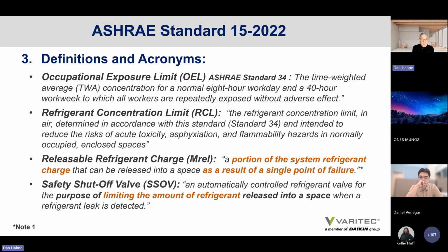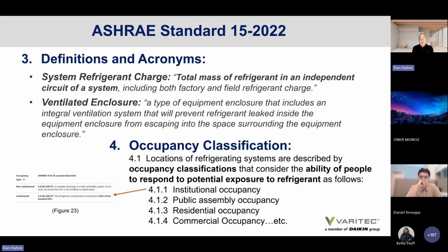There's releasable refrigerant charge, and this is an important component in evaluating whether or not a VRV system meets the RCL limits in the smallest occupied space served by a VRV system. Releasable refrigerant charge is a portion of a system refrigerant charge that can be released into a space as a result of a single point of failure. In other words, one refrigerant circuit. Another term is a safety shutoff valve, an automatically controlled refrigerant valve for the purpose of limiting the amount of refrigerant released into a space when a refrigerant leak is detected. There's also system refrigerant charge, which is the total mass of refrigerant in an independent circuit of a system.